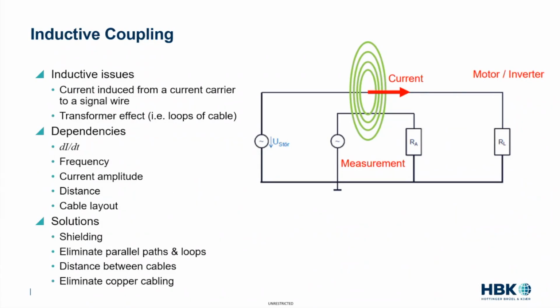So we have inductive coupling. With inductive issues, we've got current induced from a current carrier to a signal wire. You've got the transformer effect, for example, loops of cable. And it's dependent on the di/dt, the frequency, the current amplitude, the distance, and also the layout of your cables. So the solutions, again, these are just very brief. We'll get a little bit more detail on some of these solutions. And again, we will talk about an ultimate solution, which is rather exciting, near the end of this webinar. So shielding is a possible solution. You also want to eliminate parallel paths and loops. You want to make sure that you have a significant distance between the cables and the source, and eliminate copper cabling if you can do so.